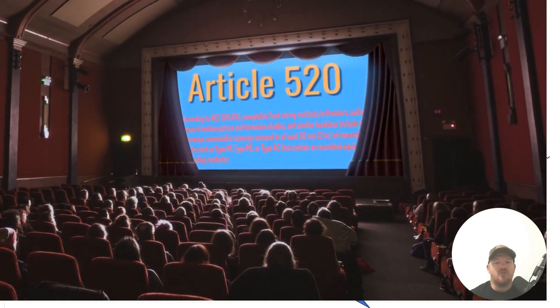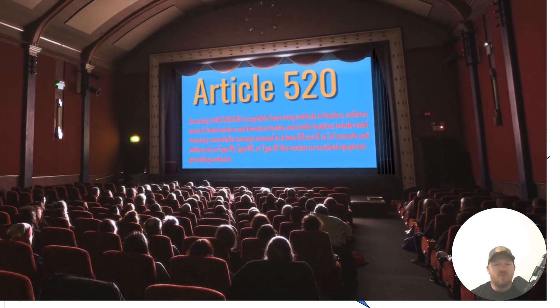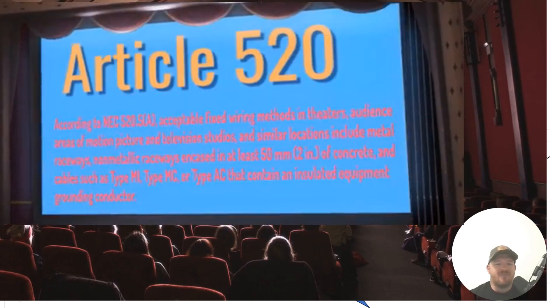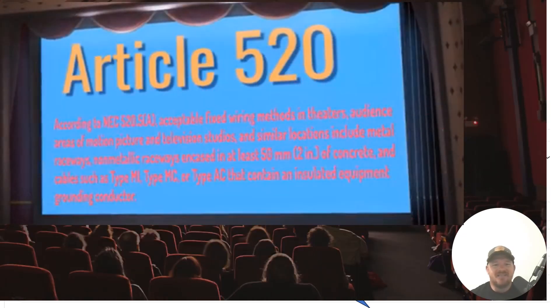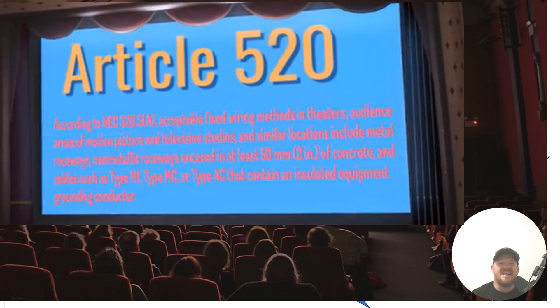Today we're heading to Article 520 for the answer to our question. In 520.5A, acceptable fixed wiring methods in theaters, audience areas of motion picture and television studios, and similar locations include metal raceways, non-metallic raceways encased in at least 2 inches of concrete, and cables such as MI, MC, and type AC that contain an insulated equipment grounding conductor.